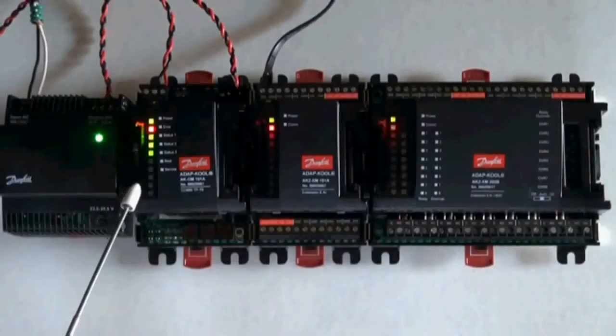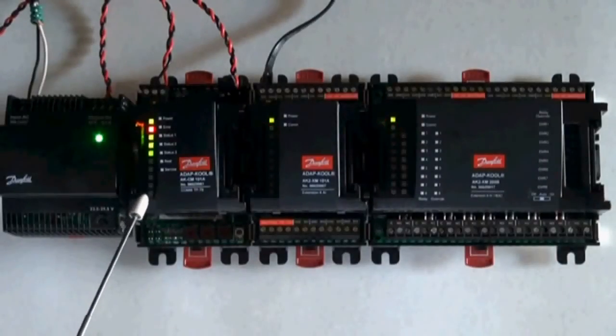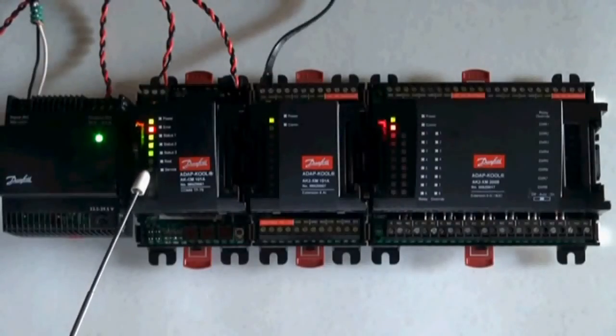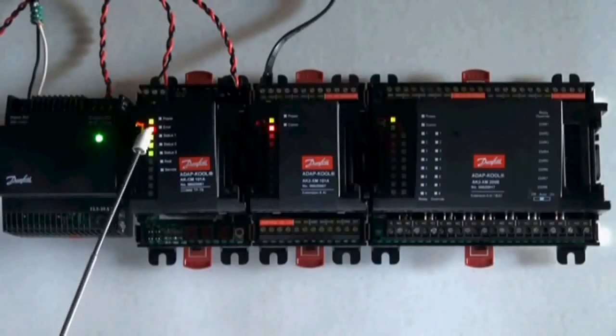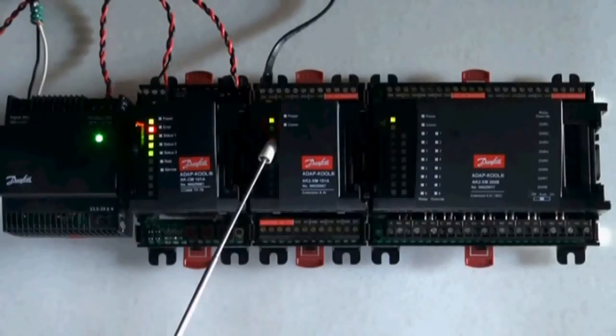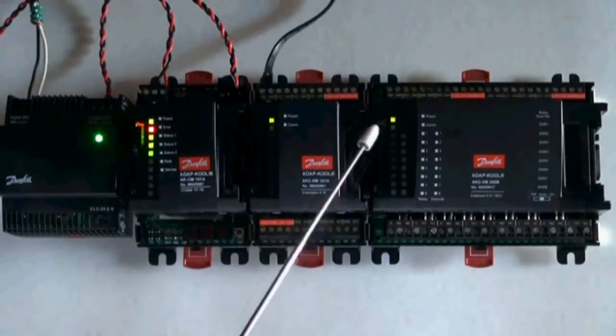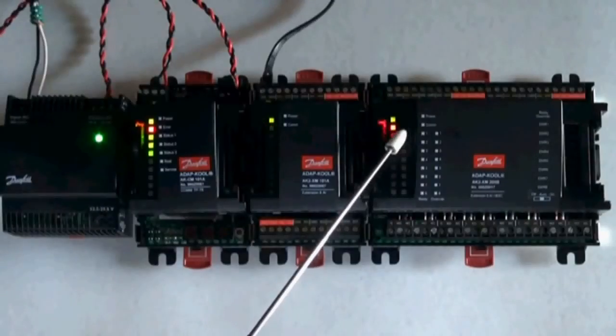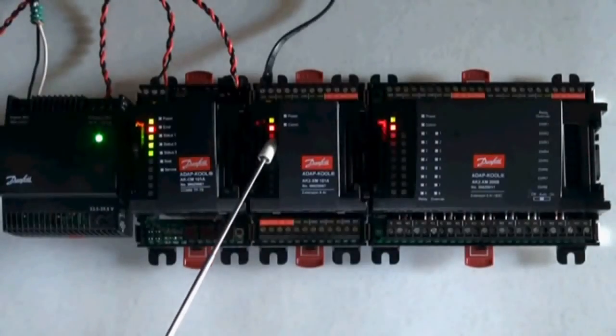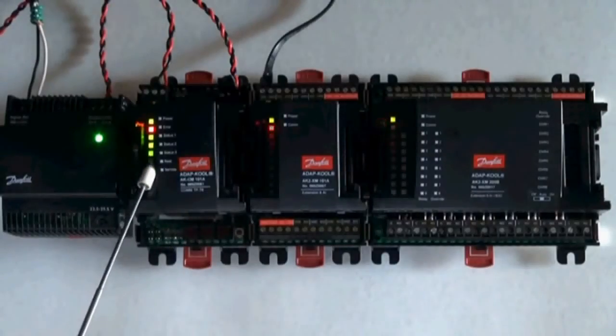This condition indicates a communication loss between the AK2 modules and the 255 controller. Note on the communication module, status 1 is on steady. This is not a normal condition, and the error light is lit. On extension modules, note the red blinking COM light. This indicates communication with the host controller, which is the 255, has been lost. To troubleshoot this condition, wiring and voltages must be checked.